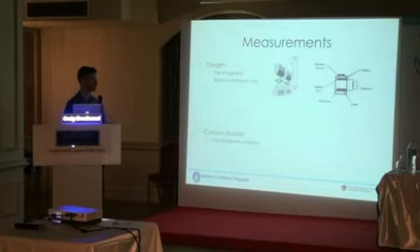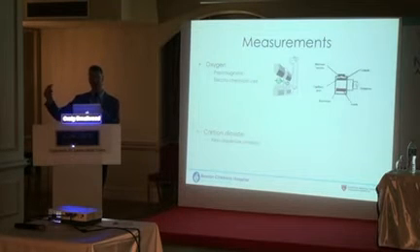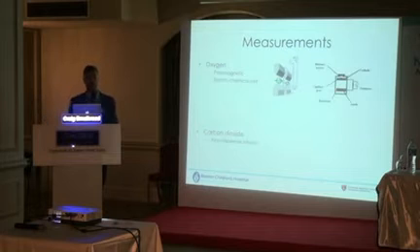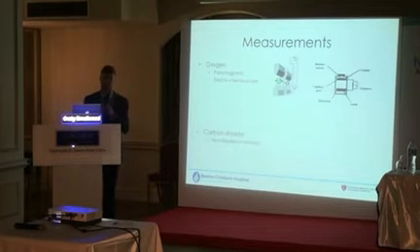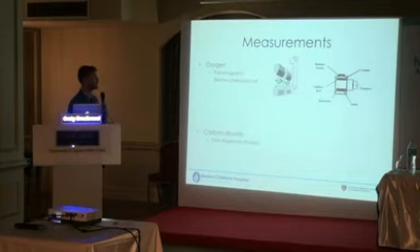Another way is every ventilator principally has a method to assess the fraction inspired of oxygen concentration, just to make sure that when you set it to 50%, you're actually giving 50%. And if you guys interact with ventilators a fair amount, you'll know that from time to time that device fails, or it tells you that there's an error or discrepancy between that which you set and that which you are measuring in the patient's ventilator circuit. But this is the device.